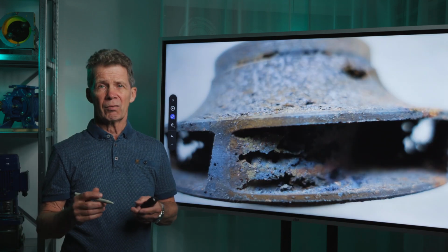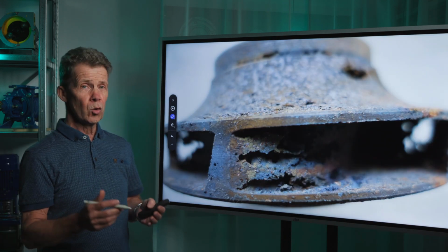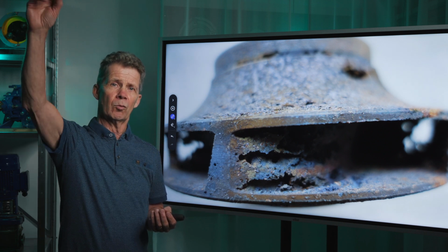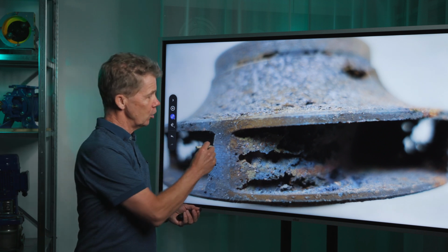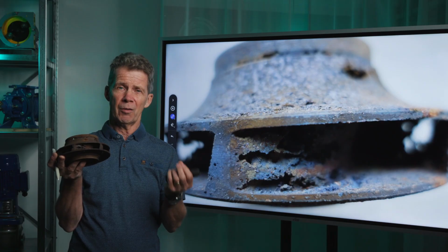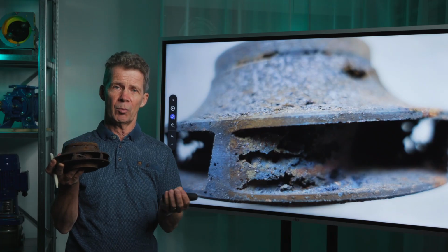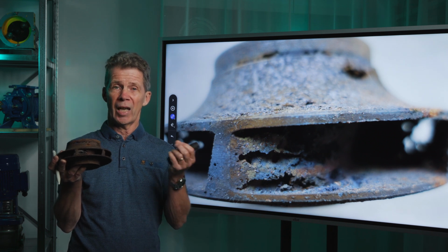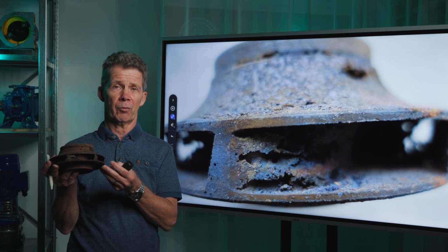If something happens in your suction line, also there your pipe friction will be higher and higher. Then you will have an impeller like this. Like you see here, holes in the impeller caused by cavitation. And that was because of a higher pipe friction than calculated. Therefore, the NPSH available in the system is not sufficient anymore for the NPSH required for the pump curve. So it's really important to know if you are dealing with scaling, yes or no.